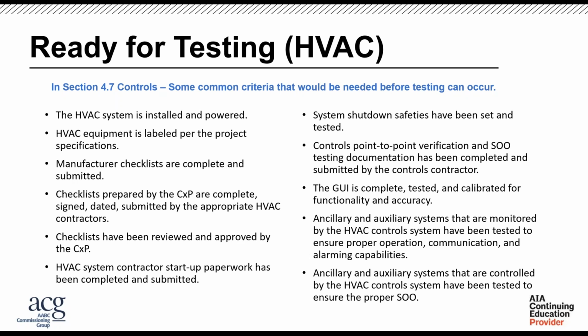But you want to make sure that they're running through everything: system shutdown, safeties, and that your graphical user interface is complete, tested, and calibrated for functionality and accuracy. Your ancillary and auxiliary systems that are monitored by the HVAC control systems have been tested to ensure proper operation, communication, and alarming capabilities. And alarms, make sure those alarms are checked. When we come there as a commissioning provider, this should not be the first time we're verifying some of the alarms, some of the points.